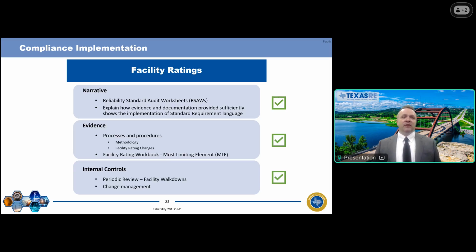And so if we have an incorrect MLE identified, we're going to have incorrect operational limitations, which could impact system operations adversely and lead to either a line inadvertently tripping or not using the capacity of that facility to its design, to its most capable.